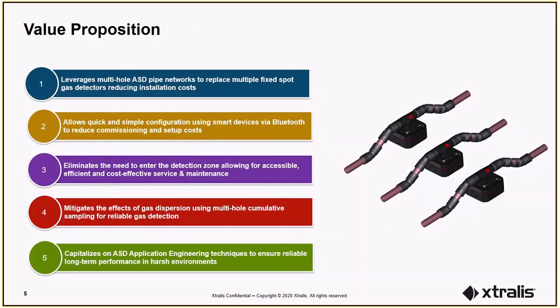Due to its ability for aspirated and multi-point sampling, VESDA Sensepoint XCL brings unique benefits to the customer. Lower installation cost due to multi-point sampling, where one VESDA Sensepoint XCL gas detector can replace several spot gas detectors. Lower commissioning cost by using an app on your smart device for quick setup, commissioning, and maintenance. Lower maintenance cost due to aspirating sampling. The VESDA Sensepoint XCL can be installed outside the detection zone for easy access, saving time and money for service and maintenance. Reliable detection for dispersed gas in ventilated spaces due to cumulative sampling. Reliable long-term performance because the detector is protected against the harshness of the environment. Let's take a closer look.